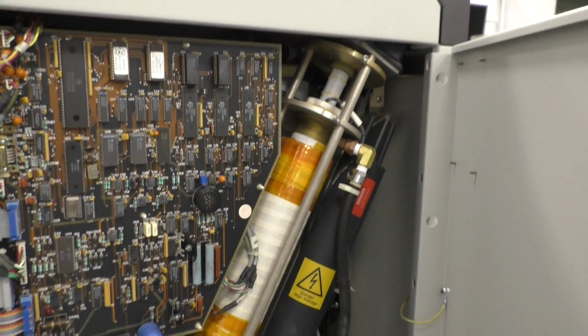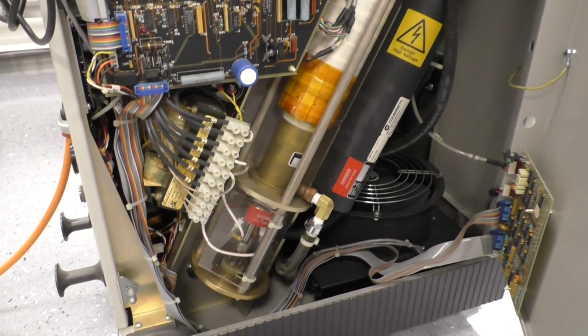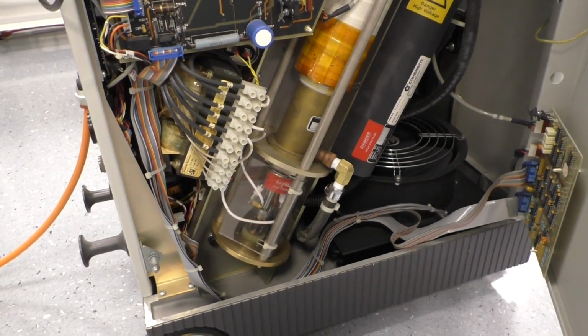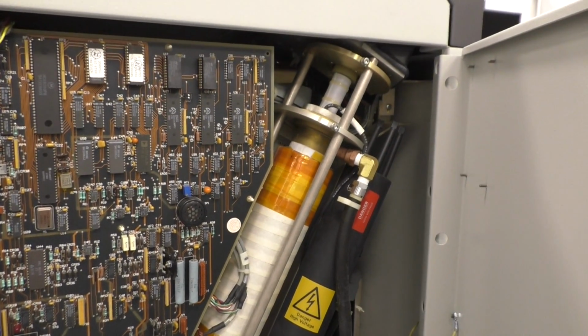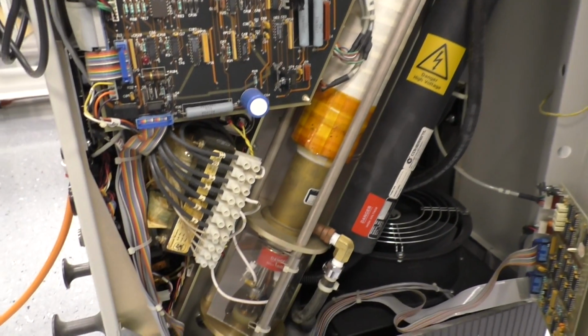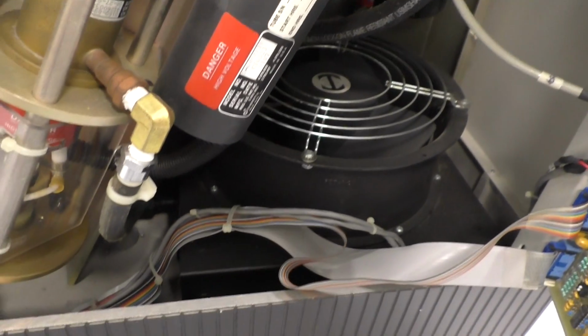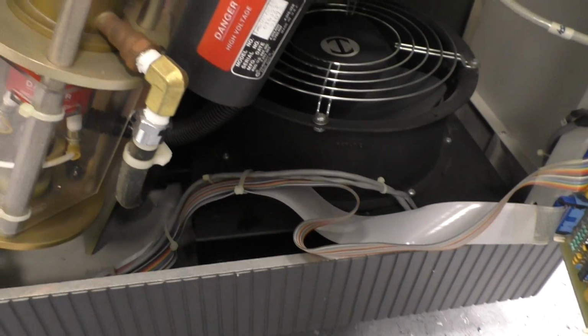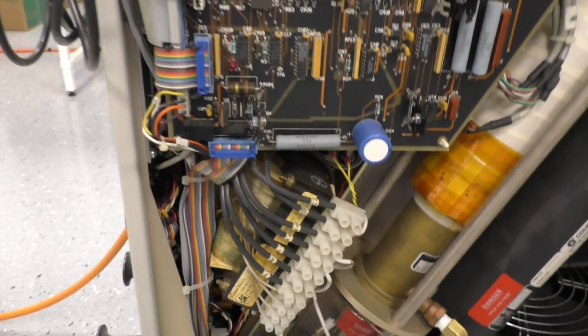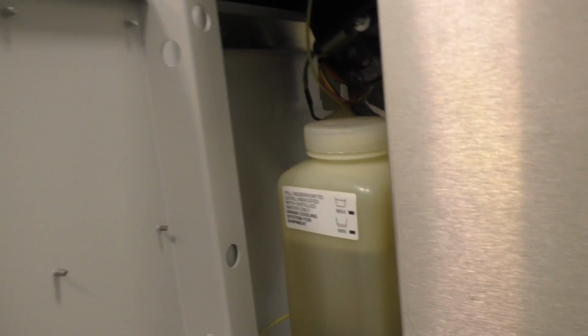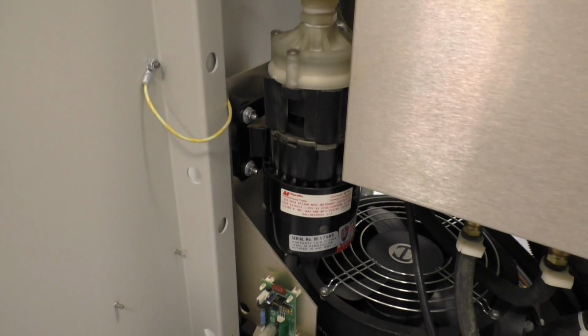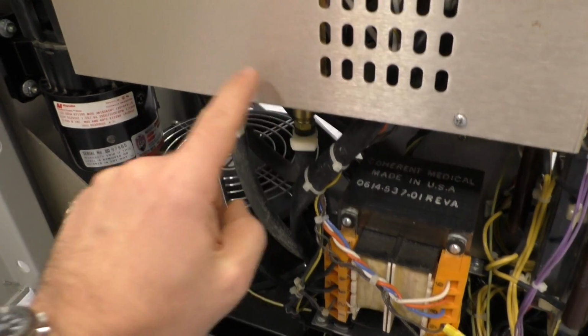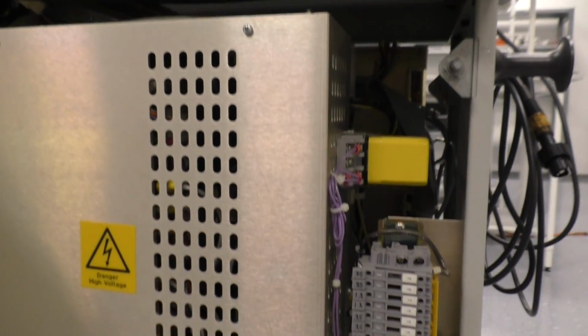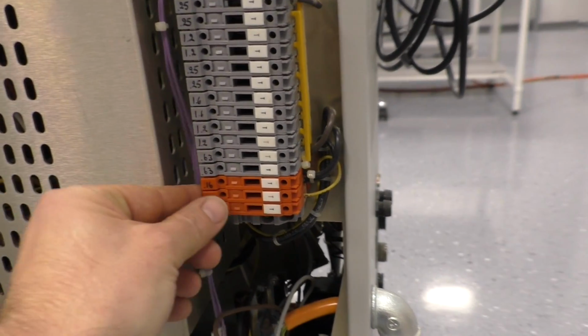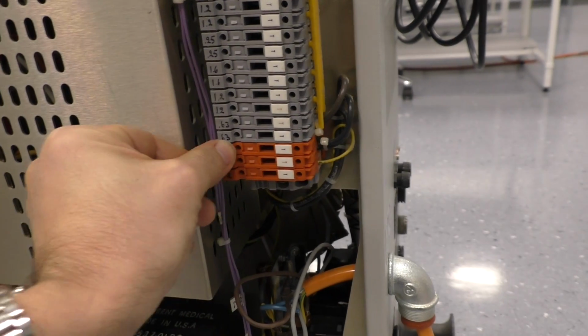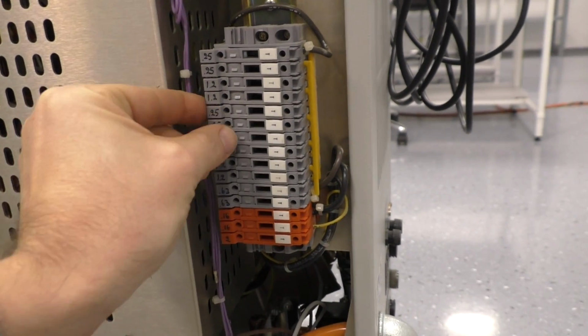And here is the laser tube. It's a liquid-cooled Argon laser, 2.5 watt output power and many kilowatts of input power. We have a big fan down here with a water cooler radiator underneath that cover here. On the other side we have a water reservoir, cooling pump, water pump. We have also water cooling for the electronic box here, which is the laser power supply. And here are a bunch of fuses in an interesting drawer-like compartment.